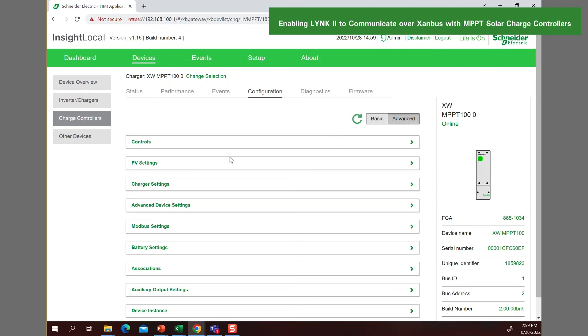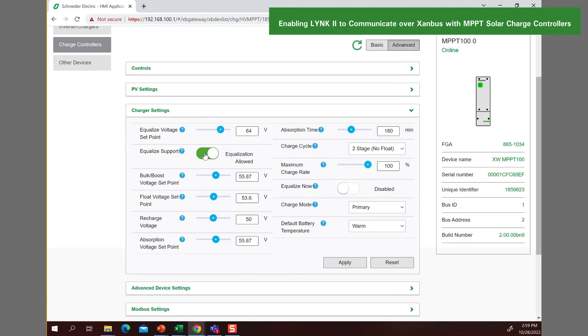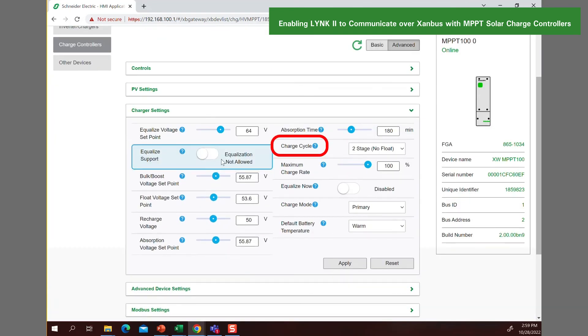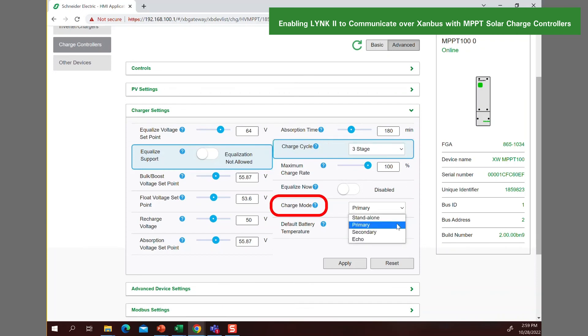Now we can set up the MPPT charger settings. The recommended charge cycle setting is three stage, which after the batteries are full, will enable DC current for loads to be available from the PV system. The recommended charge mode setting is primary, which will set the PV charging as the priority source for charging.